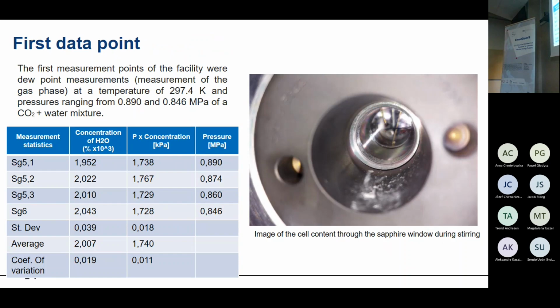And we generated the first data point. The first measurement points of the facility were dew point measurements of the gas phase at a temperature of 24 degrees, and the pressure was around 9 bars. We had very good results. The standard deviation is really low, so it is very promising for the next measurements. And here you can see the image of the cell content through the sapphire window during stirring. Here is the gas phase, and here is the liquid phase, CO2 and water. So we have the VLE.